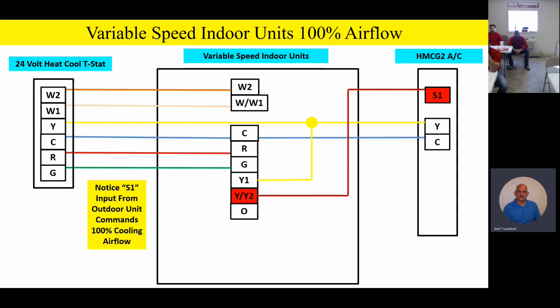So the straight cooling product is very, very straightforward. I mean, it's very simple. You'll notice you just have 3 wires going outside. That S1 wire to command second stage airflow, yellow and common going outside. And you get all that functionality. Any questions or comments on how the HMCG2 wires up with the indoor products that we talked about? Any questions or comments? We're all good.